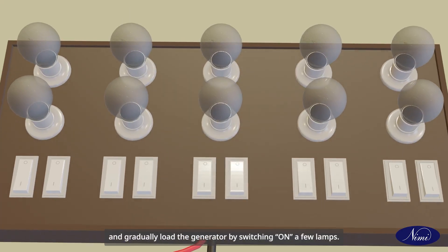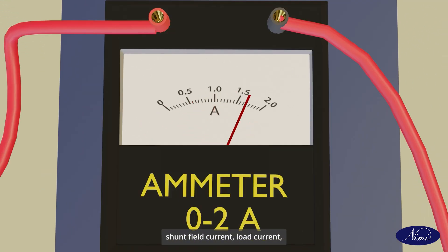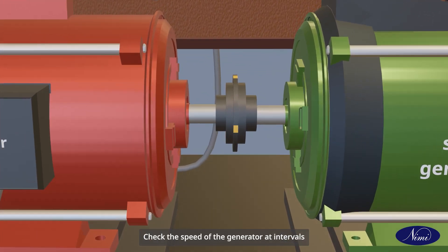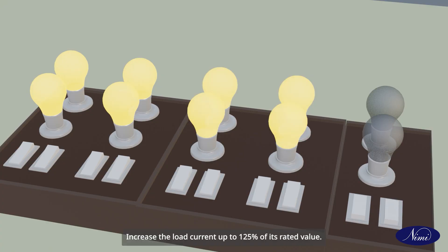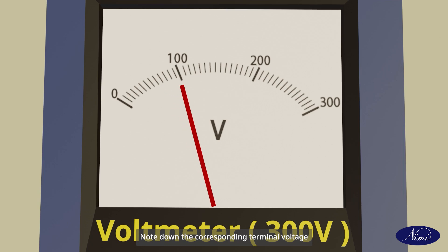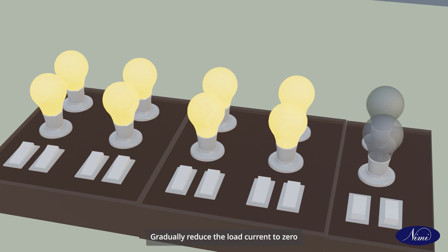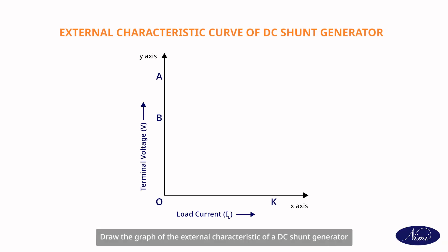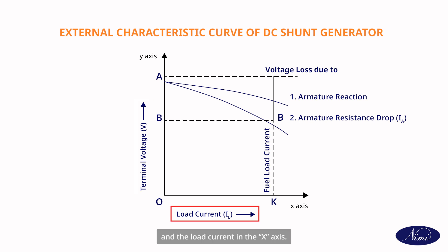Close the load switch and gradually load the generator by switching on a few lamps. Read the corresponding terminal voltage, shunt field current, and load current, and record them in tabulation. Check the speed of the generator at intervals and adjust it to the rated value. Increase the load current up to 125% of its rated value, noting down the corresponding terminal voltage and field current for each step. Gradually reduce the load current to zero and switch off the load circuit and the prime mover. Draw the graph of the external characteristic of the DC shunt generator, keeping the terminal voltage on the Y-axis and the load current on the X-axis.